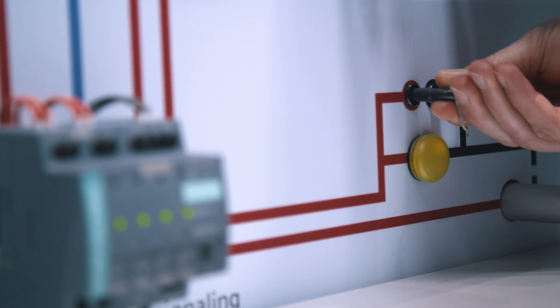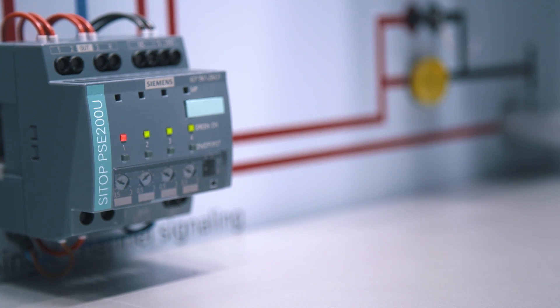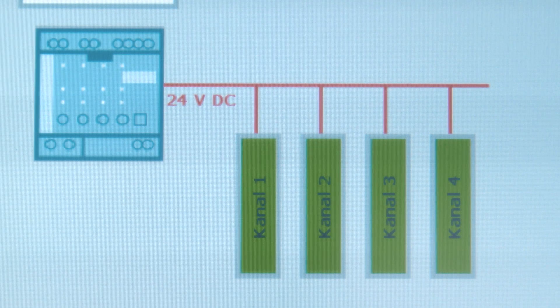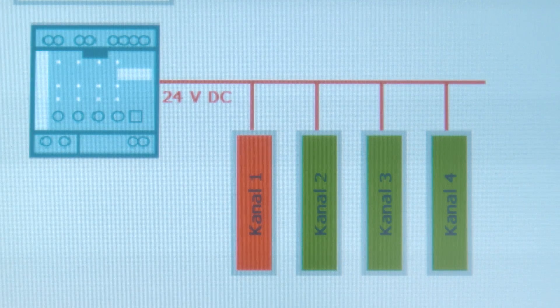The SITOP selectivity modules divide the load current into several consumer circuits and monitor them electronically for overload and short circuit. A faulty output is immediately turned off while the other outputs continue to be supplied without interruption, helping to prevent a total failure of the application. A channel-specific status message is possible via only one digital input in the PLC.